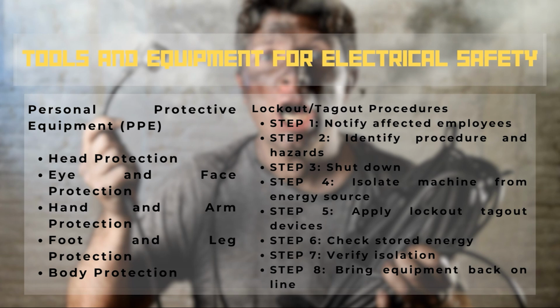First, check that no personnel can be exposed to the threat of an energy hazard. Then verify isolation by trying to operate it. Step 8 is to bring equipment back online. Make sure that the machine or equipment is fully reassembled. Then check that the tools have been cleared from the work area.